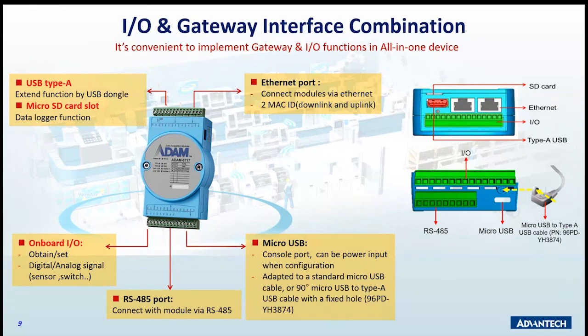It obtains set digital analog signals from sensors or switches. It includes the RS485 port for your legacy devices or any legacy serial buses you might have. Dual Ethernet links, so you can have one going to a network and one going to an intranet type scenario if you need to, and separate the two. There's a micro USB port on the end, which is a console port that can also be used to power the entire device, using a standard micro USB cable. It has a little screw hole there so you can put in a micro USB cable and actually screw it into the device, so if you're in a vibrational type scenario and must use USB, you can do it.